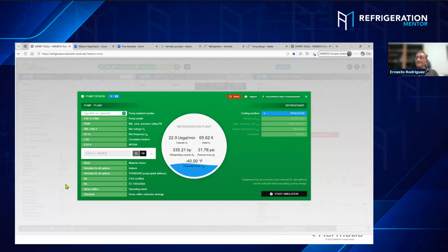And according to your system, whether it requires high loads or low loads, the pump is going to respond to move the capacity of liquid the system needs. Those changes in capacity also require keeping a very static level on the suction of the pump. Plus, when the defrosting system starts and the regulator valve opens to release the hot gas back to the vessel, we sometimes have pressure differentials. To prevent that turbulence when we have defrosting of some loads, we need to keep the pump safe to prevent cavitation.